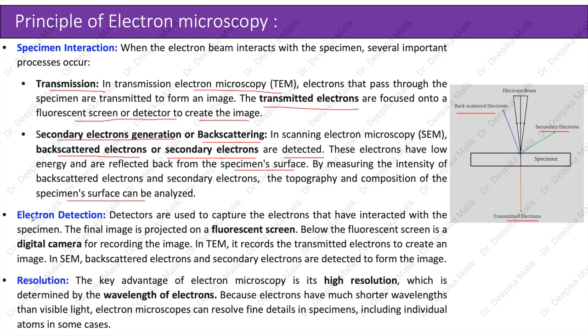Electron detection: detectors are used to capture the electrons that have interacted with the specimen. The final image is projected on a fluorescent screen. Below the fluorescent screen is a digital camera for recording the image. In transmission electron microscopy it records the transmitted electrons to create an image; in scanning electron microscopy, backscattered or secondary electrons are detected to form the image.